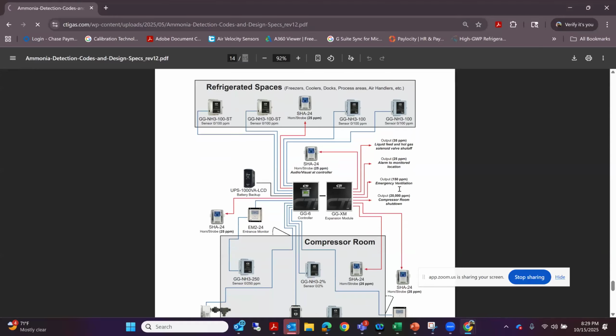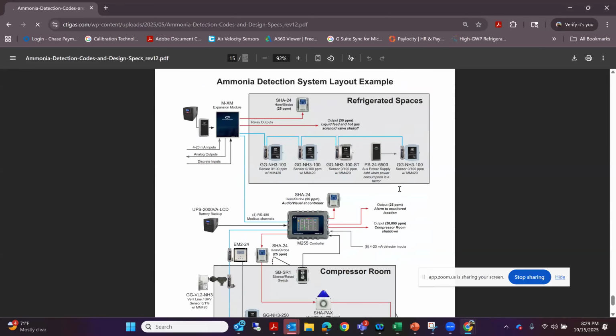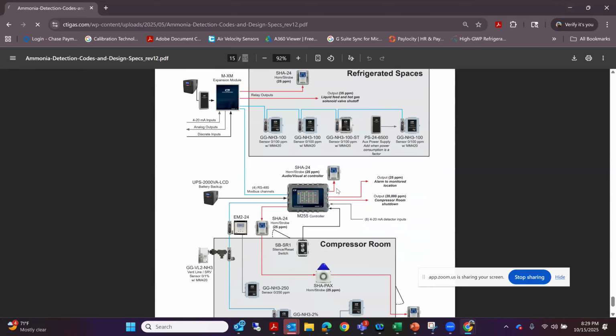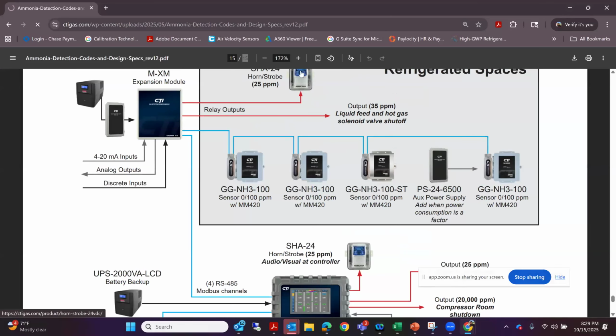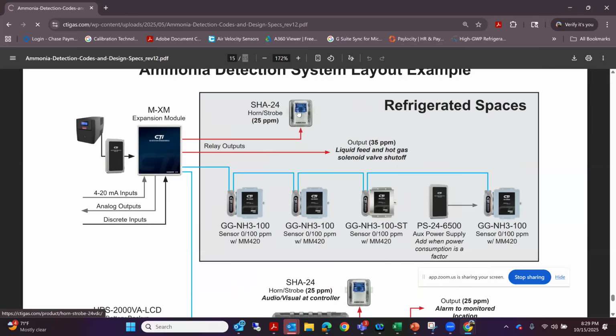Modbus systems are a little bit different, and in that way they allow you to actually daisy chain these sensors with a module here that can be addressed uniquely with an 8-position dip switch. What's nice about these Modbus systems is that for future expansion, if somebody came in and said, hey, we didn't have enough of these horn strobes, we would really like to have some of these horn strobes carried on from out here off the same circuit, but maybe it's another 300 or 400 foot at the other end of the building.